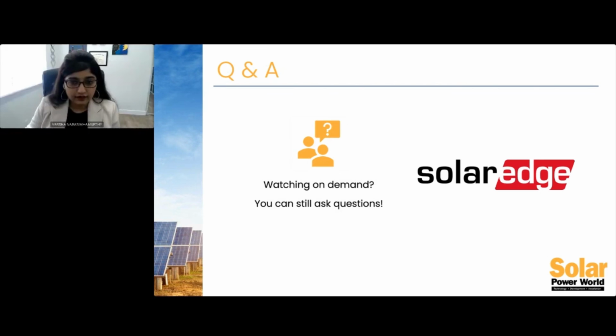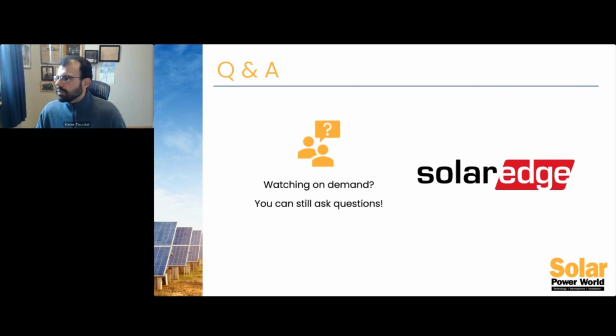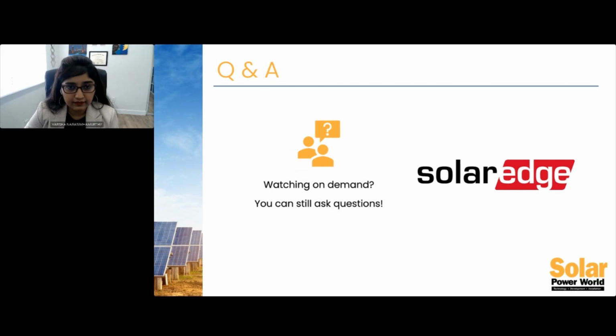Let's see. What is the DC operating current per string? And I know, Kleber, you did touch on this. Yeah, the DC operating current is 20 amps. So it's 20 amps per string. And there is a question about whether this is able to handle different string lengths.